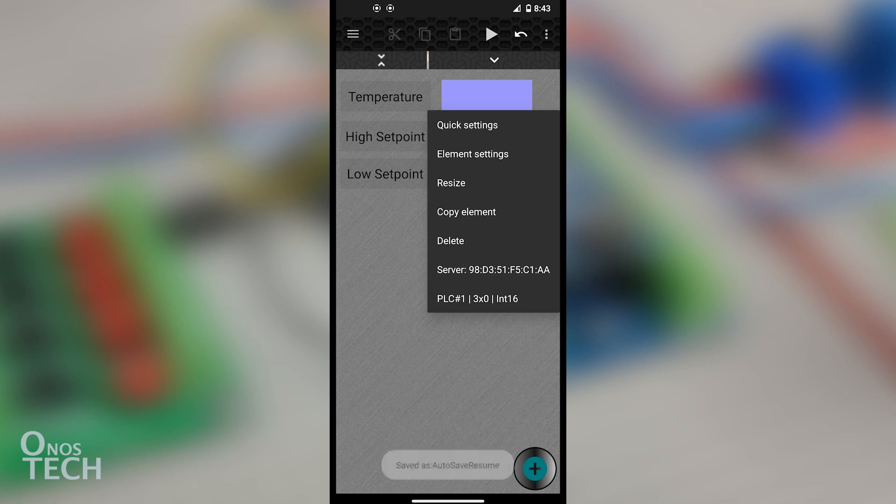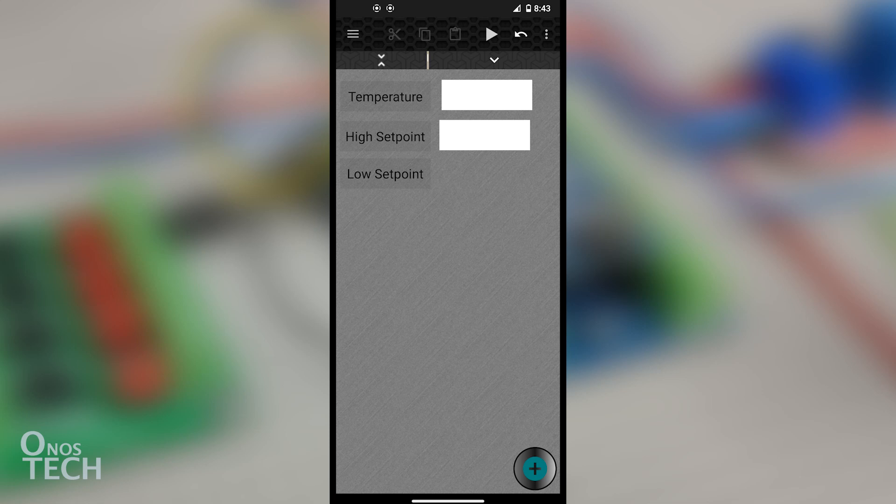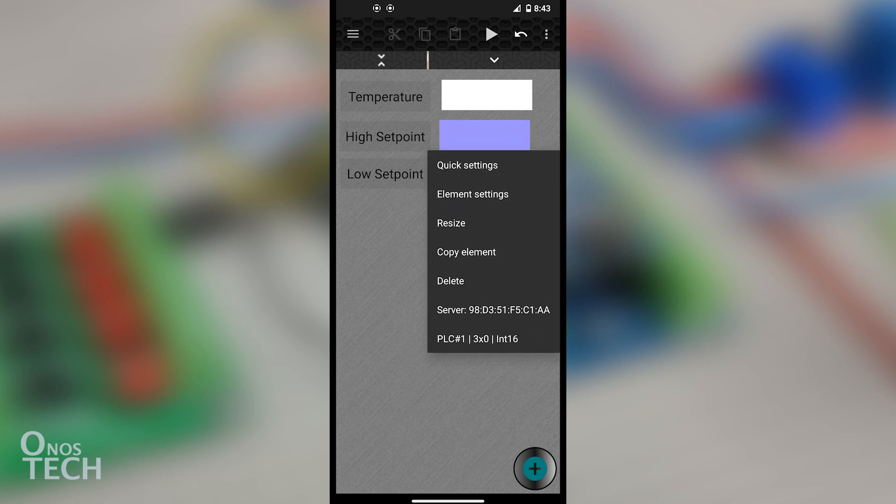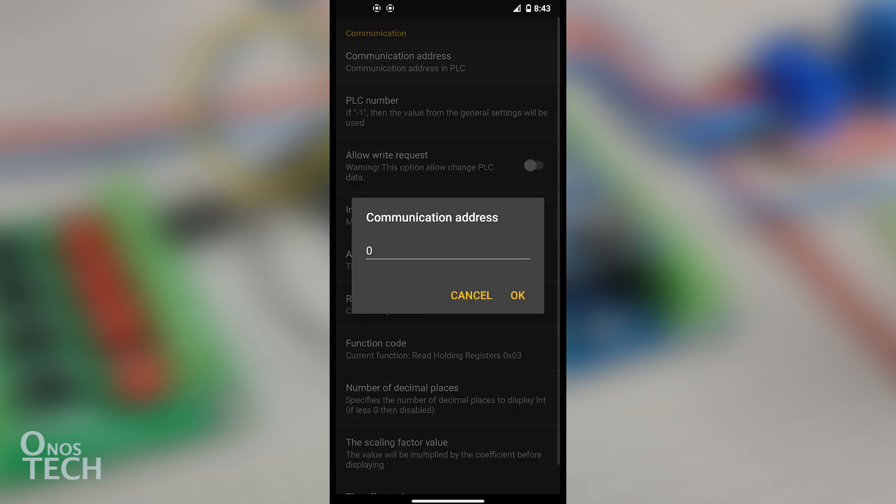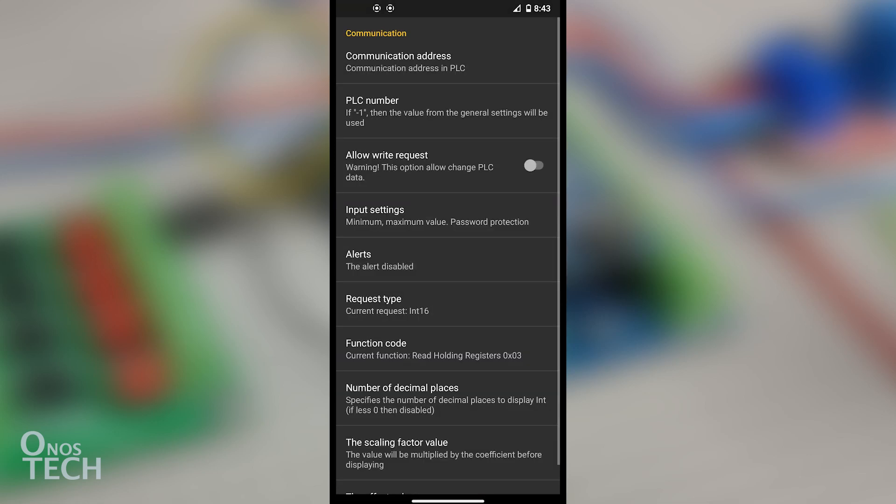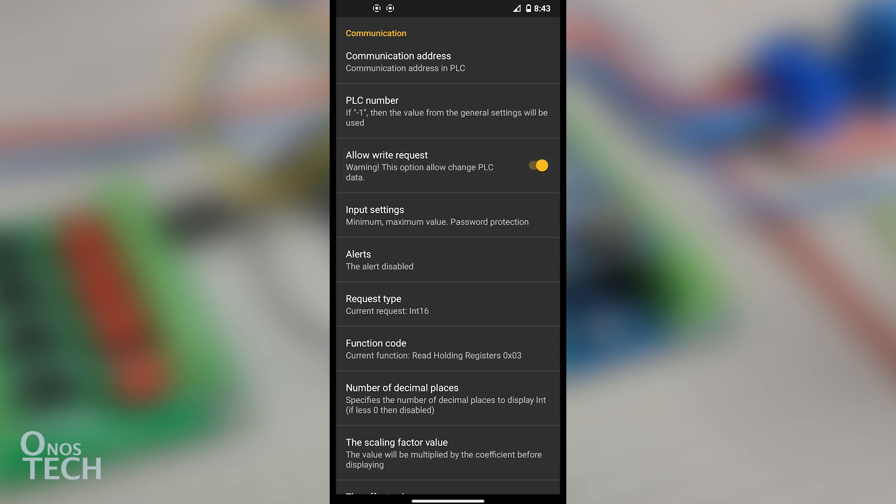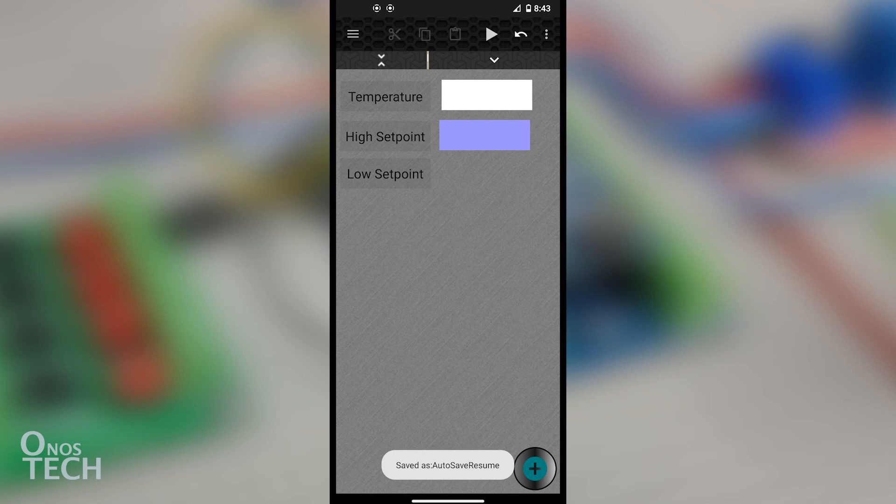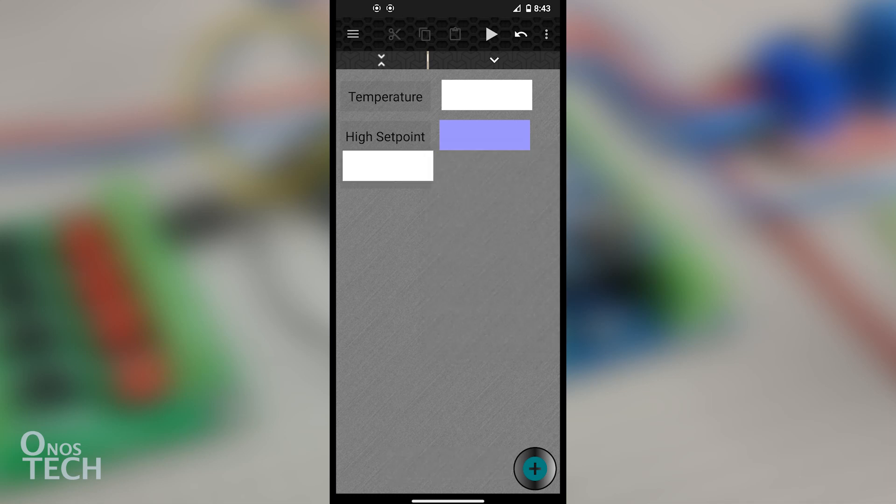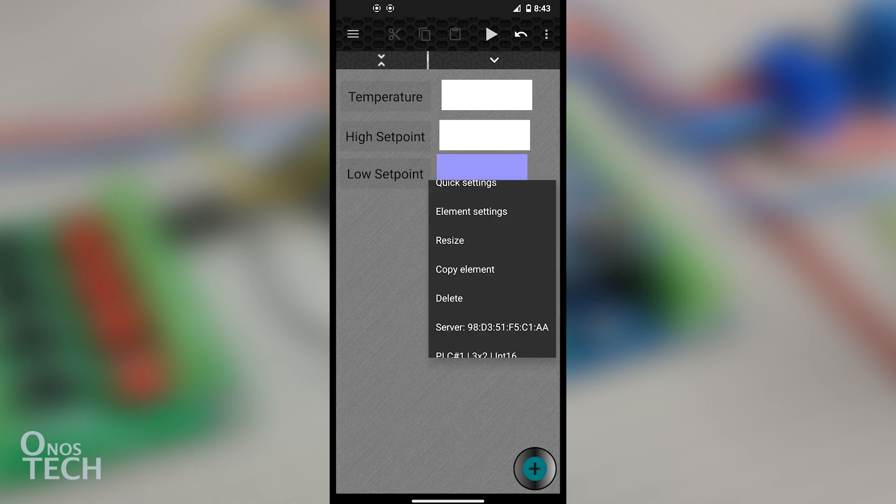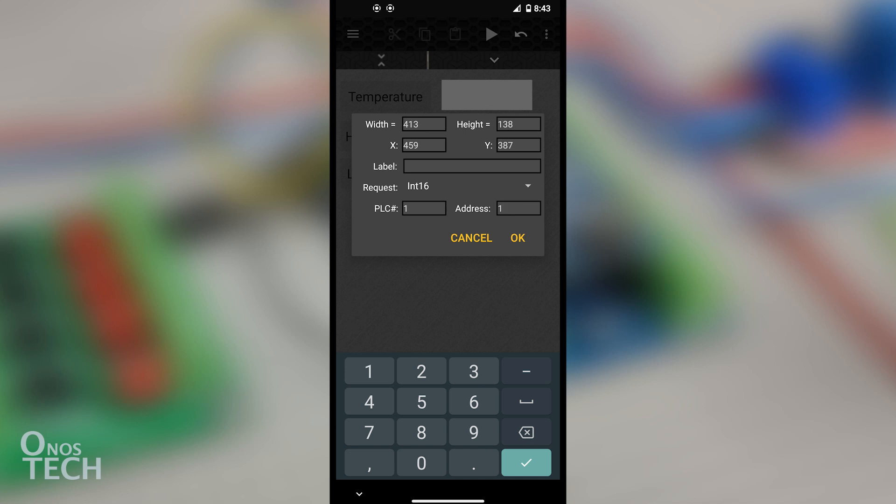Copy the NUM input and place it before the High Setpoint. Touch it and select PLC#1, 3x0, INT16. Change the Communication Address to 2 and enable Allow Write Request for changing the setpoint. Copy the High Setpoint NUM input and place it before the Low Setpoint label. Change the Communication Address to 1 from Quick Settings.